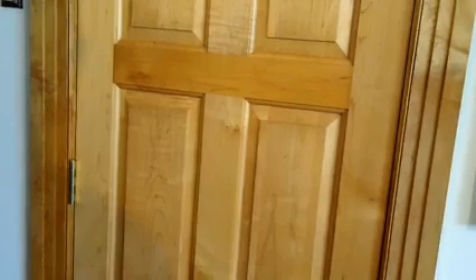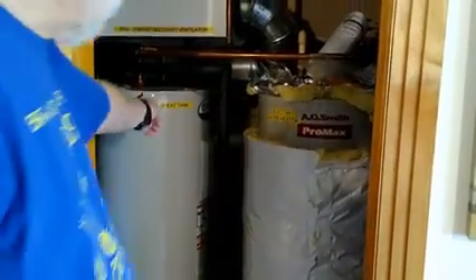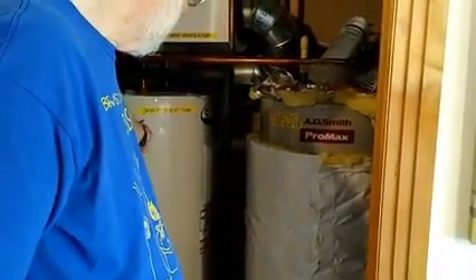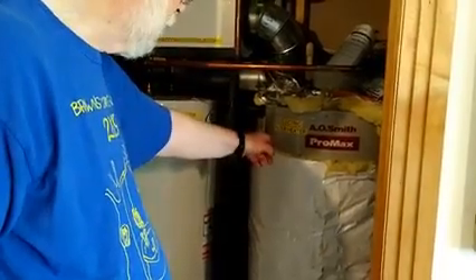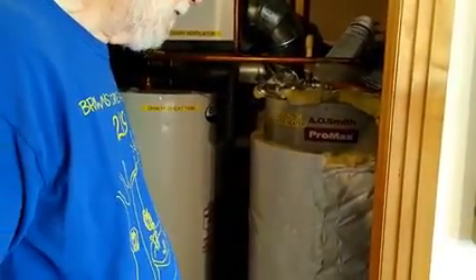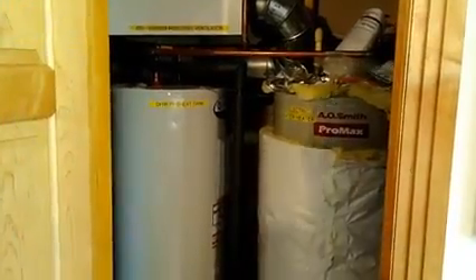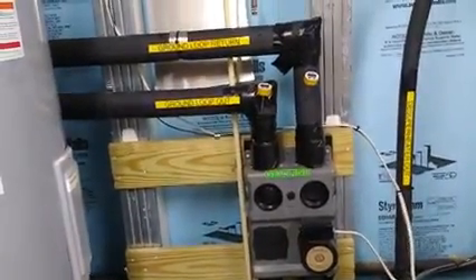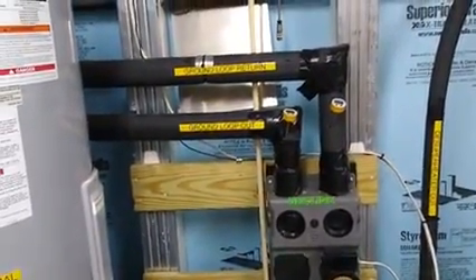The geothermal system has 2 features which I consider to be pure serendipity. The first is the de-superheater, which delivers a stream of waste heat via hot water to a preheat tank in a domestic hot water supply, providing hot water feed to the electric water heater, thereby reducing the amount of electricity used. The second bit of serendipity relates to the seasonal thermal cycles of the ground loop with its 3 200-foot wells.